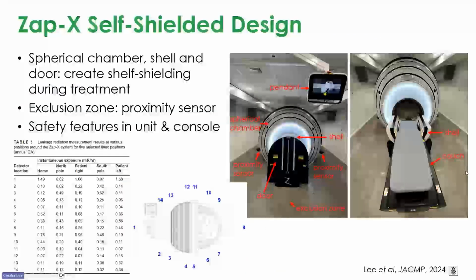So when the patient walks in, the couch is typically out, and then we set up the patient and send the patient in, and then the shell and the door are closed. So this spherical chamber and the shell and door create self-shielding during treatment. And there is an exclusion zone around the unit. Outside the exclusion zone, the radiation level is pretty low. So during commissioning, we performed the radiation survey outside the exclusion zone at different gantry angles. You can see the exposure rate was all under 2 milliroentgen per hour.